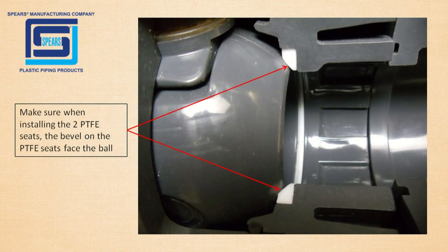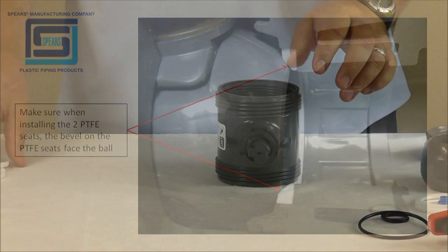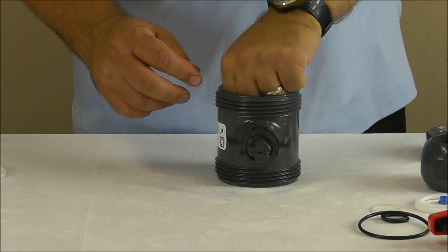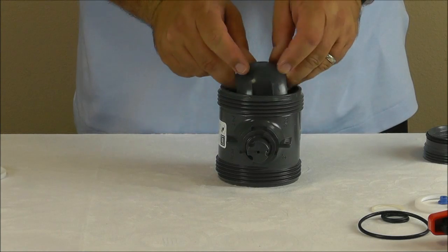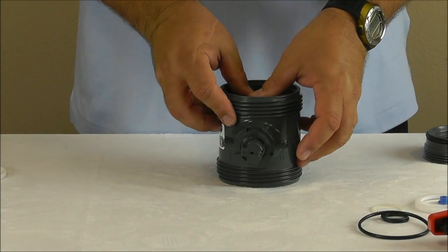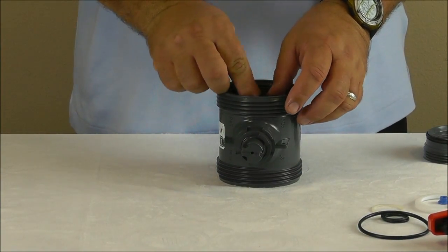Make sure when installing the PTFE seats, the bevel on the PTFE seats face the ball. Install one of the new PTFE seats and then reinsert the ball by lining up the stem drive and slot at the top of the ball. Install the second PTFE seat.